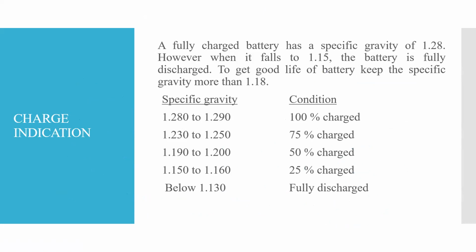Okay. A fully charged battery has a specific gravity of 1.28. When it is fully discharged, it goes to less than 1.15.